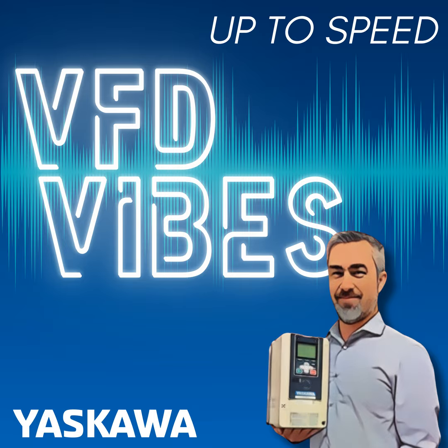Well, the spec called for a filter, so you had to leave the filter attached to the back panel, but it couldn't be connected to anything, or that would bring the noise right into the back panel. So, yeah, every once in a while you run into something that's strange. Well, that's what's funny about specs, they often are written for one particular device. The spec says the drive needs a filter or whatever. It's not taking into account what else is in the panel, how things are grounded and bonded in the panel. It's not even taking into account the power system configuration.